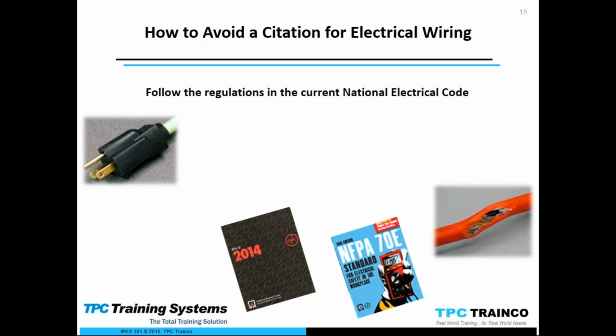It says follow the regulations in the current National Electrical Code. That's pretty good if you're in construction under 1926, where you're installing equipment. But if you're in general industry, maybe the equipment's already installed. So you might want to look at the National Electrical Code and determine whether the equipment was installed properly, especially grounding and bonding, which is very important for worker safety.